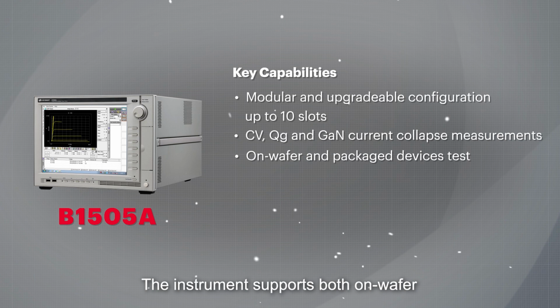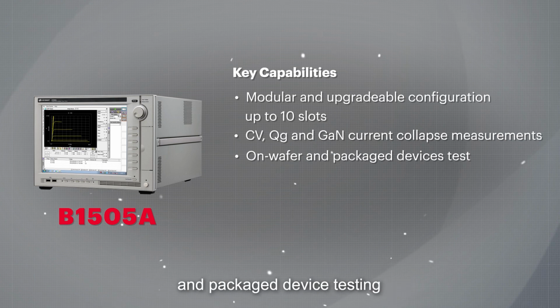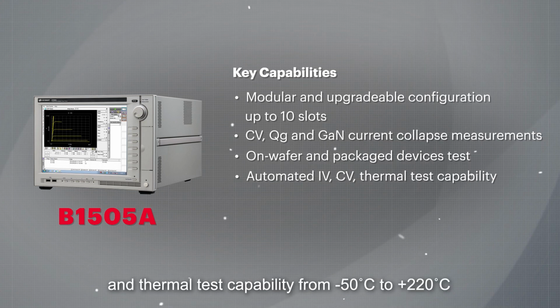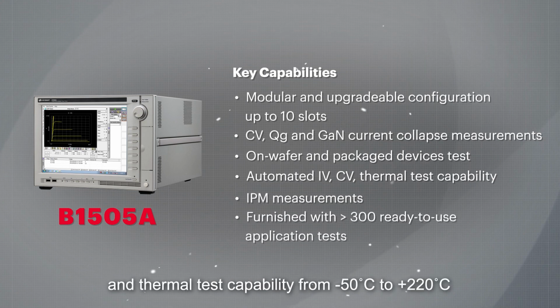The instrument supports both on-wafer and packaged device testing with automated IV, CV, and thermal test capability from -50 degrees Celsius to 220 degrees Celsius.